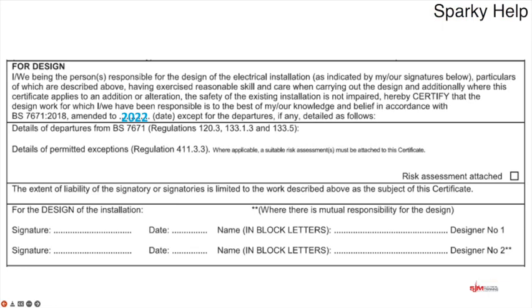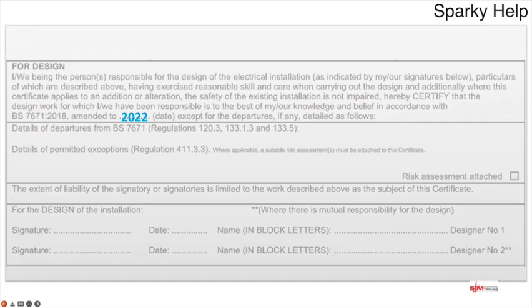That's easy enough, that's straightforward. Next bit down, details of departures from BS 7671. BS 7671, remember, is guidance only ultimately. It's only in a court of law where it would be tested against you and used as evidence. So it says details of departures from BS 7671, regulations 120.3 and 133.1.3 and 133.5. So let's have a look at each of those and see basically what they are referring to.